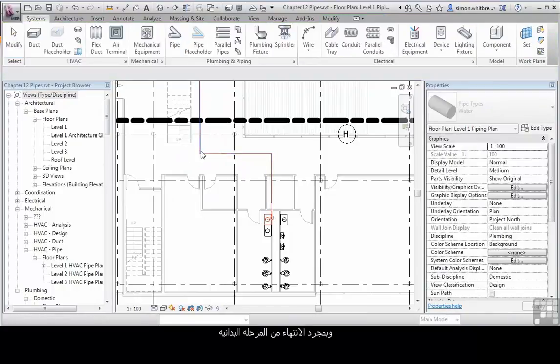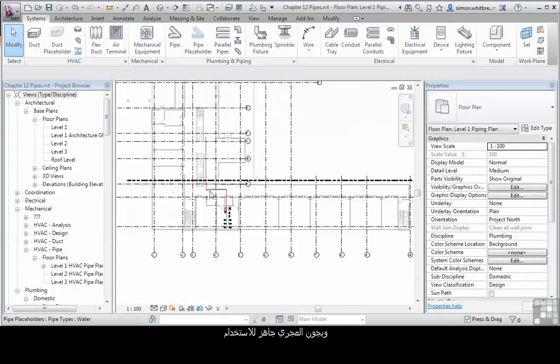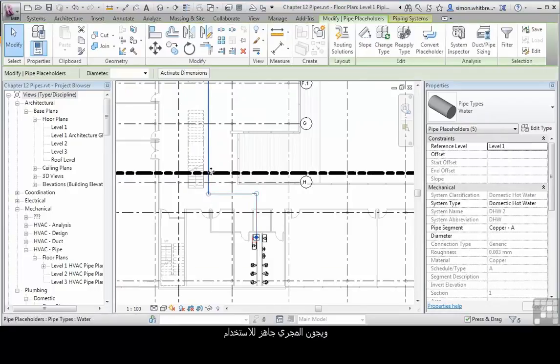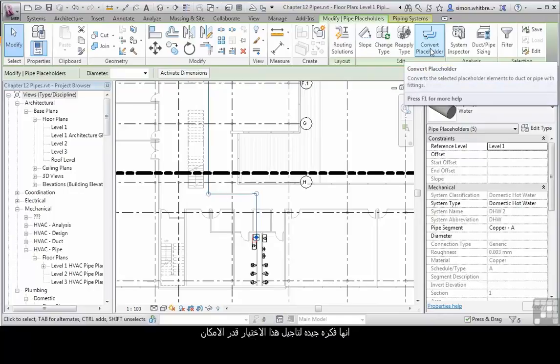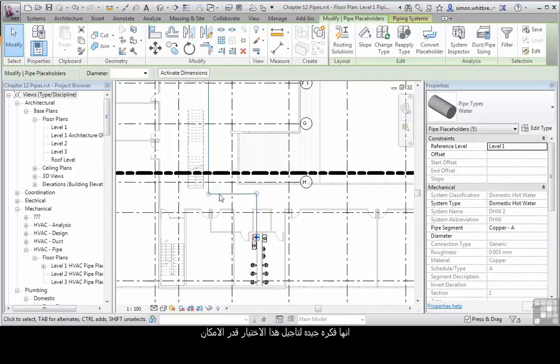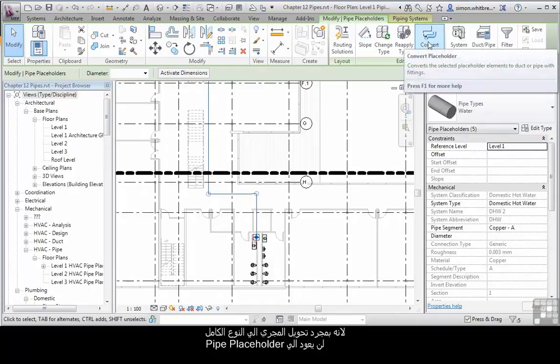Once I've got through the conceptual stage and my pipe run is ready to be used, I can convert that run using the convert placeholder tool. It's a good idea to leave this as long as possible, as once you've changed those to full pipes there's no going back.